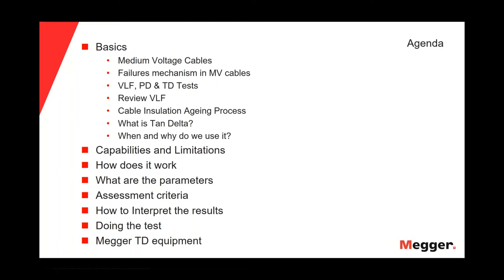Then we will move to how it works, what the parameters involved in the tan delta are, the assessment criteria for the tan delta, and finally we will go to how to interpret the results, how we do the tan delta test, and finally the tan delta equipment that we have in Megger.